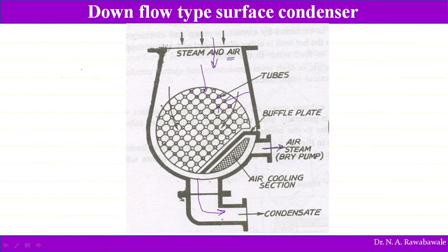Steam is 99%, and say for example 1% is the air. So as this steam gets condensed, automatically vacuum is created. Because of vacuum, the condensate has to be removed forcibly, or it has to be sucked using a pump, and the air gets separated from condensate or water, and that is to be removed by using a dry pump.